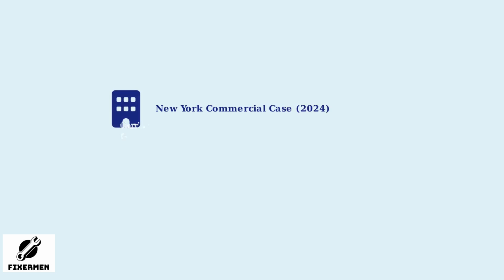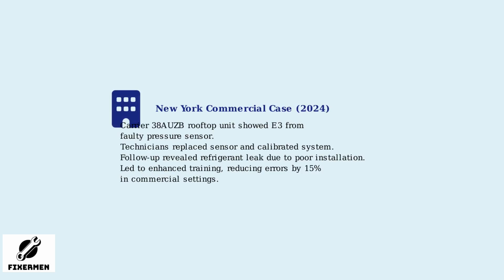A 2024 incident in a New York office building involved a Carrier 38AUZB rooftop unit that triggered an E3 error due to a faulty pressure sensor. Technicians replaced the sensor and recalibrated the system to resolve the immediate issue. However, a subsequent audit uncovered an underlying refrigerant leak caused by improper installation. This case prompted Carrier to implement enhanced training programs for technicians, resulting in a 15% reduction in similar errors across commercial installations.